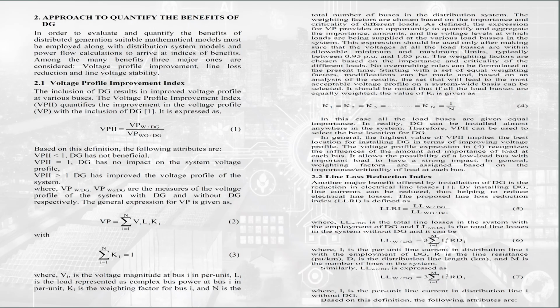Based on its definition, the following attributes are: if PI is less than 1, DG is not beneficial. If PI is equal to 1, DG is not beneficial and has no impact on the system voltage profile. If PI is greater than 1, DG has improved VP. In general, the highest value of PI implies the best location for installing DG in terms of improving VP.